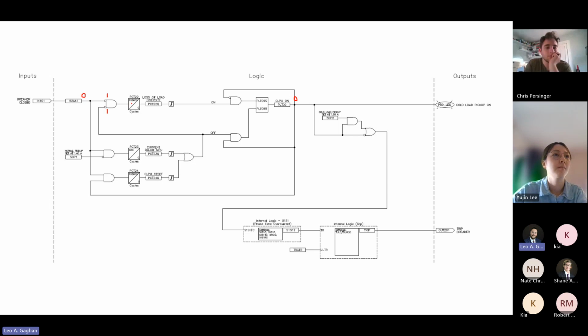If that's the case in this situation, it's for 15 minutes. So if that breaker is open for 15 minutes, right? Let's say that 15 minutes is just a time long enough to let your house get unbearably hot, right? On that hot day. If that breaker is open for 15 minutes, we're going to get to this rising edge trigger. We had a 0 here initially, which makes that a 1. And for one cycle, after 15 minutes of that breaker being open, we'll have a 1 right here.